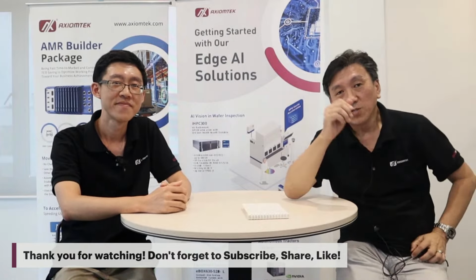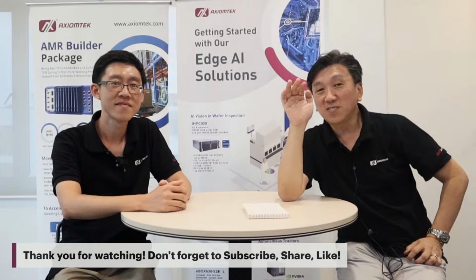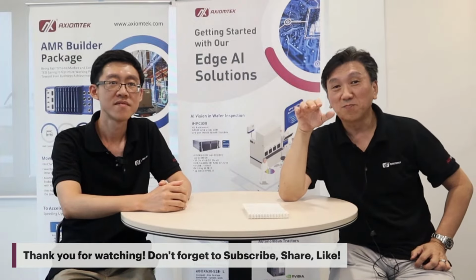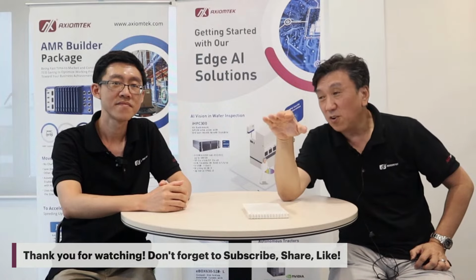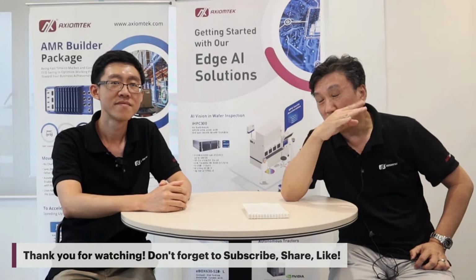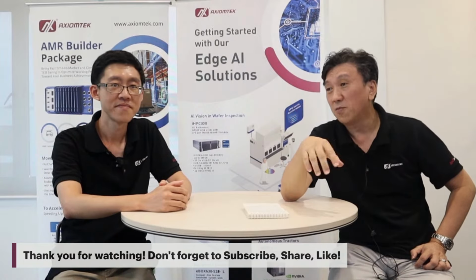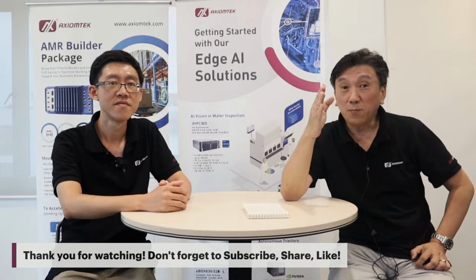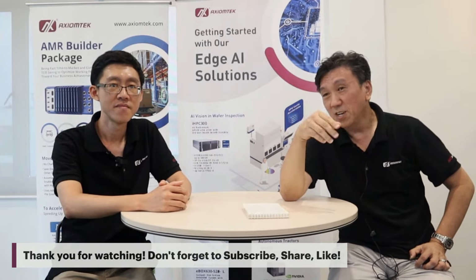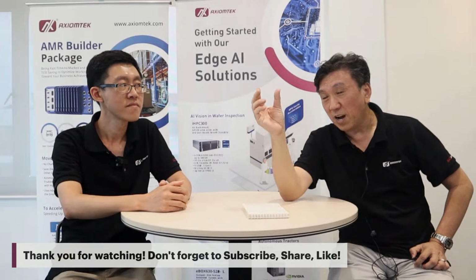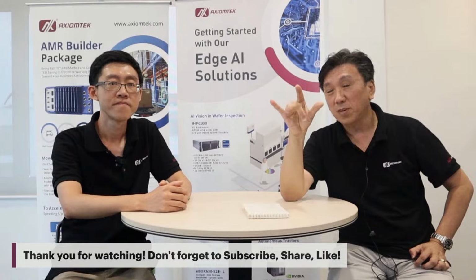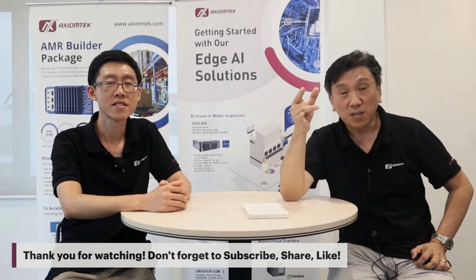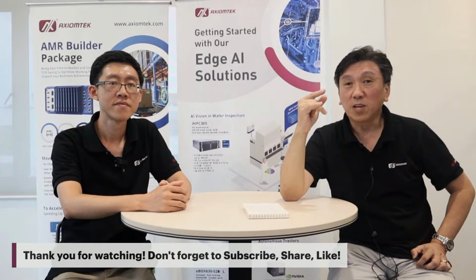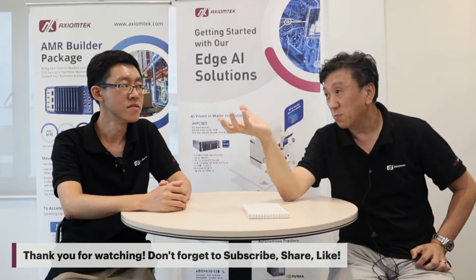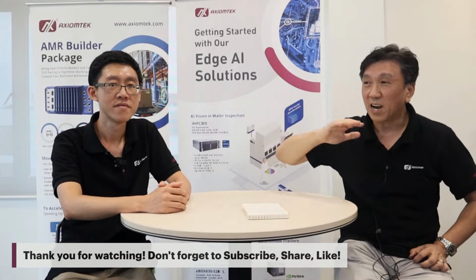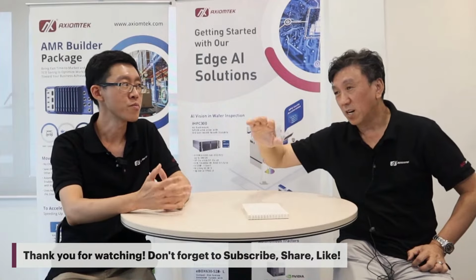I see. So that is the OEE tracking system that we have. As you can see, from a shop floor, it was simulated using what they call stack lights and some inputs that were created. Then it comes to our stack light tracker. One IoT gateway can support multiple of them. In this case, we are supporting 16 of them, right? Yes, we are able to handle 16. From there, the data is published to the local SCADA dashboard that you can visualize. You can do trending, alarming, and even reporting.